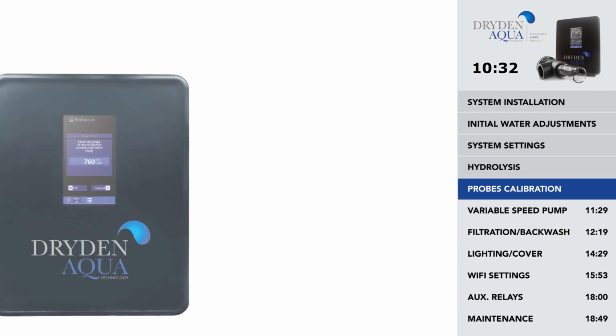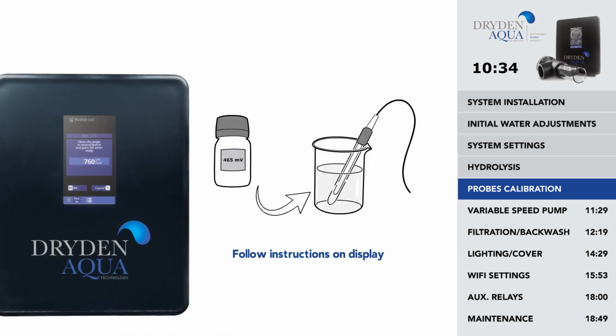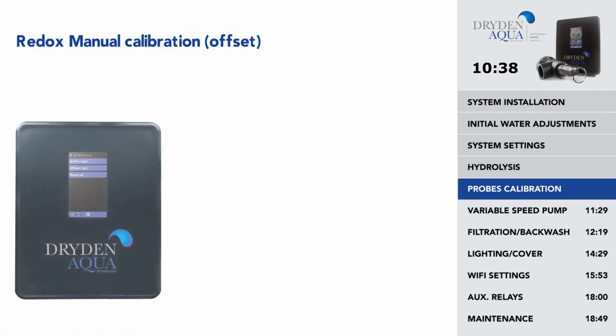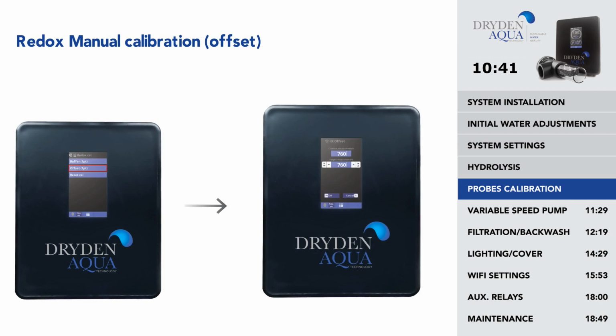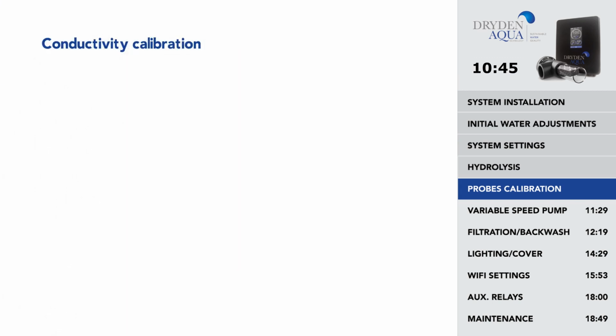Press on buffer and follow the instructions that appear on the display. Manual calibration of the redox probe is also possible, but is not recommended. Conductivity calibration.